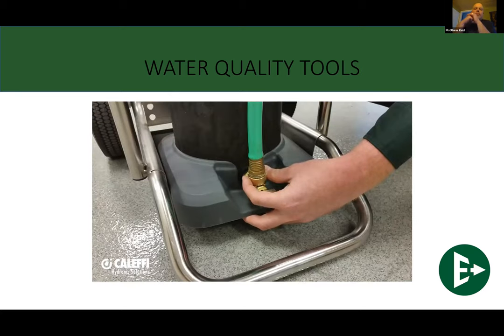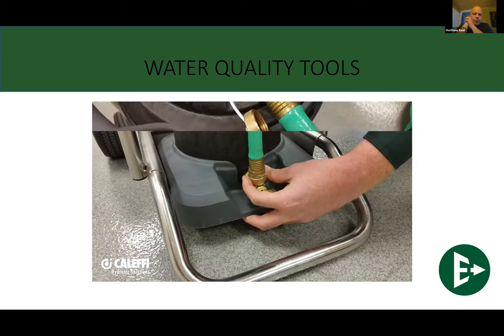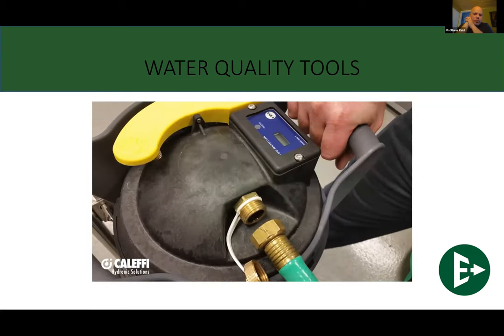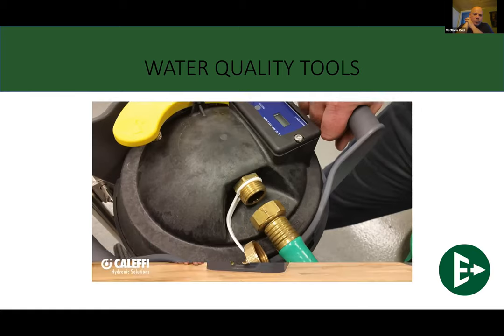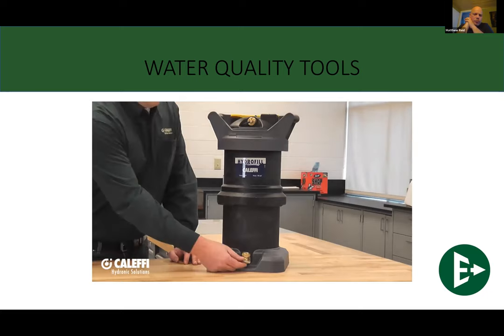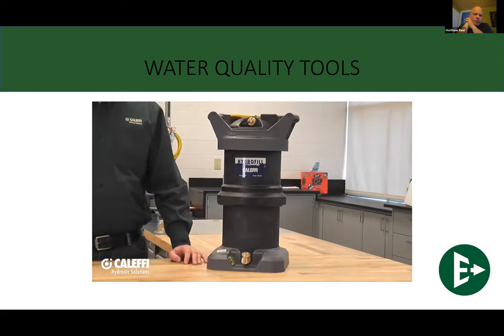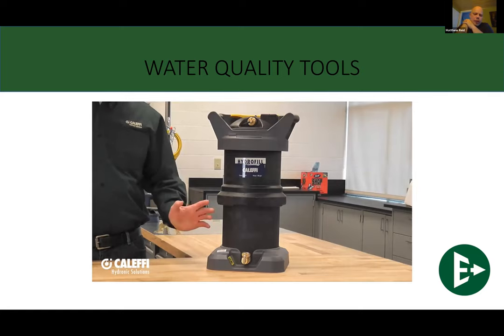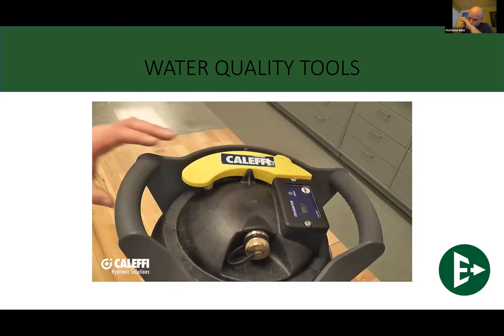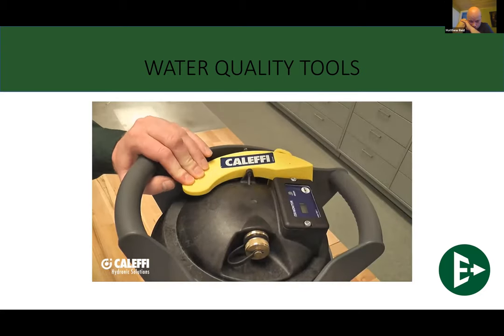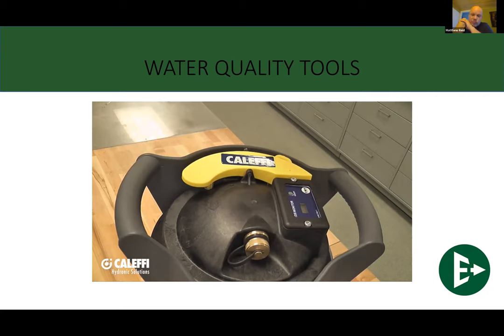Operation of the Hydrofill is pretty straightforward. You're going to connect your site water up to the bottom connection here, and then out of the top, you're going to take that to your fill point of your system, or if you're using the demineralized water, to blend with glycol. Once you've made your connections to the Hydrofill, you're going to want to slowly open the valve at the bottom of the unit. At this point, you're going to want to keep an eye out for any leaks that might be occurring at any of your connections. At that point, you can depress the yellow lever at the top to assist in purging any air out of your hose or in the Hydrofill unit itself.